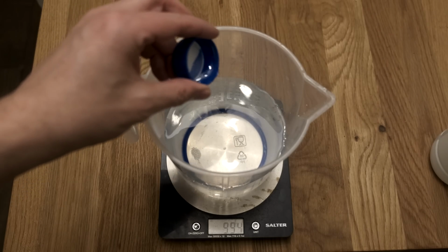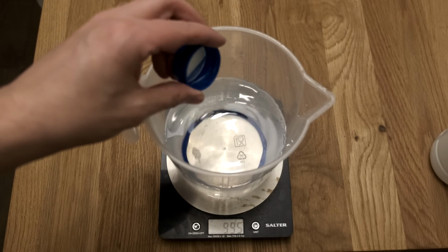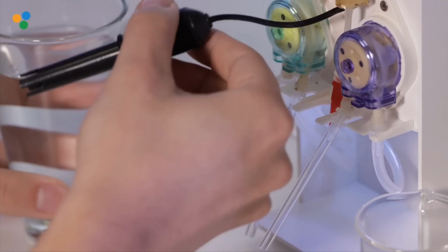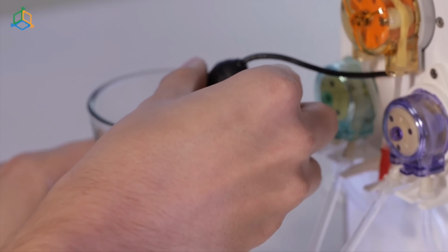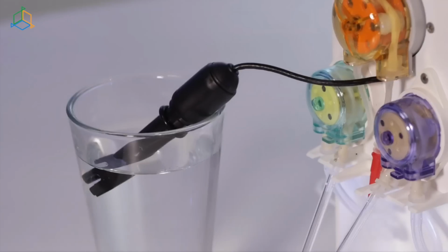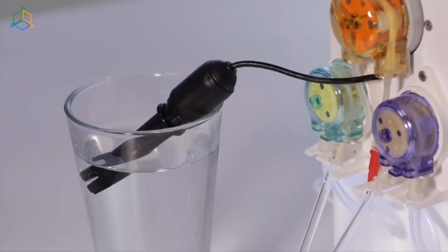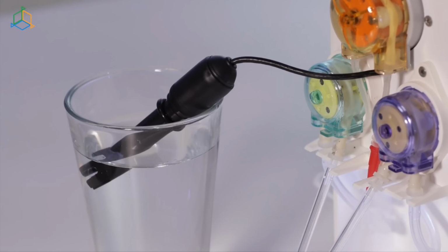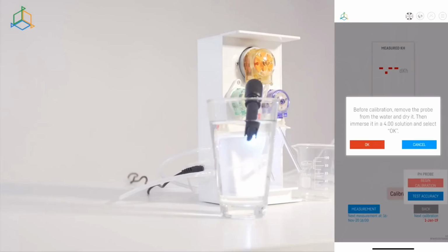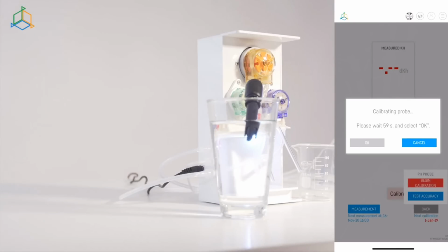I also took a little more time when calibrating the pH probe. Because the probe ships dry, I let it rest in the pH fluid for 10 minutes before starting the calibration, whereas the instructions say to start it straight away. A number of other people with the KH Keeper have done the same, and I understand Reef Factory will soon be changing the instructions to recommend you dip the probe in salt water for half an hour before you start the calibration process.